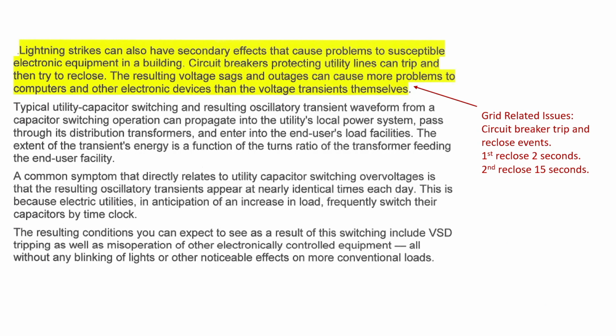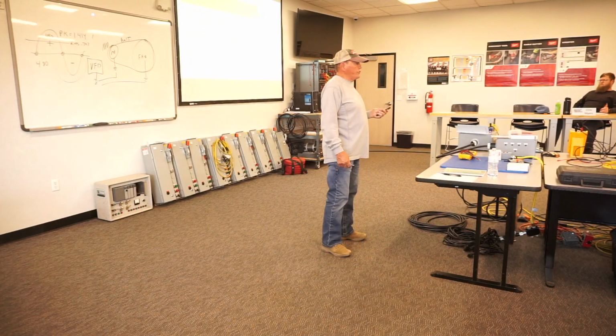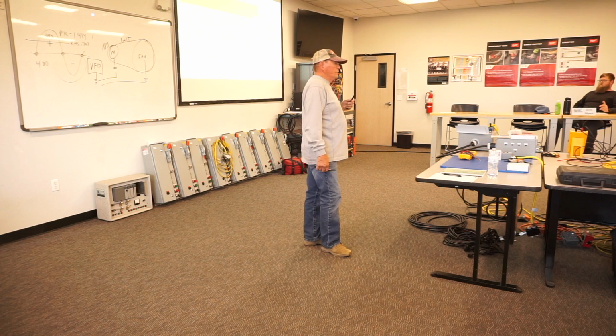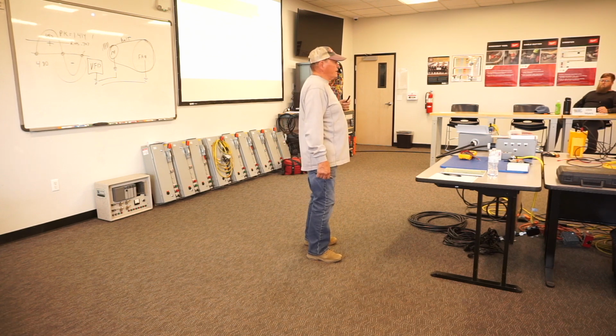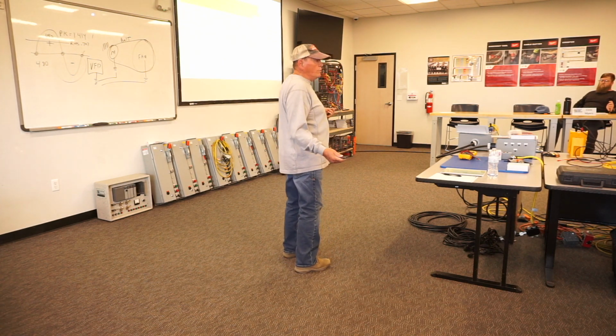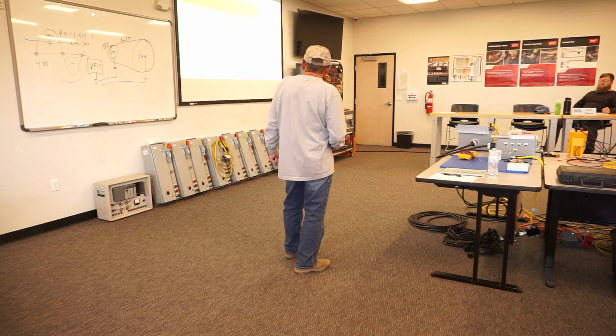And lightning strikes we're dealing with here, coming in off the grid. So without proper surge suppression, which we covered earlier, utility capacitor switching creates transients on the grid, and all those events coming in from the grid can cause grid power quality issues, which is now starting to affect LED lighting, which is the most sensitive component of our system now. Most drives can ride through these faults, but LED lighting can't. And the IT room, all the sensitive electronic equipment.